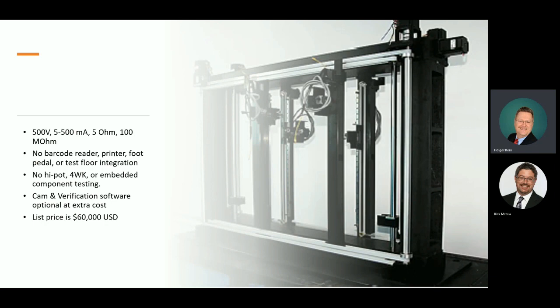So we have here basically a belt-driven system with standard parametrics for electrical measurements from 500 volt up to 100 megohms. This machine would have no barcode reader and printer, since it's a low-end machine, and also no extra test functions like high pot or 4-wire Kelvin. These would not be available for these machines, and that's the point why this is the low-end one.